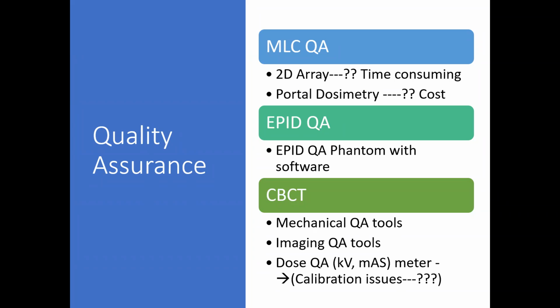And certainly if you have an electronic portal imaging device, you should have an electronic portal imaging device QA phantom with certain software to check the spatial resolution, noise, image quality, and all other things for your electronic portal imaging device. For the CBCT, most of the mechanical tools come with the machine as well. You buy a machine from Varian Medical Systems or buy a machine from Elekta, many of the mechanical tools come with the machine, but certainly while finalizing the specification sheet, as physicists, we should ensure that all these things are included in the contract.